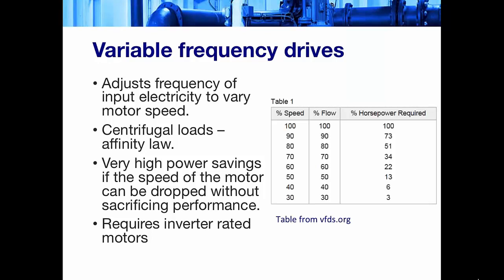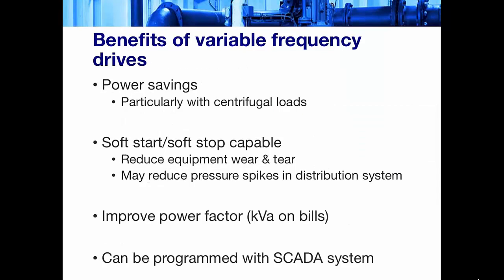It is important to note that it requires inverter rated motors in order for variable frequency drives to operate. Most newer motors are inverter rated, so there's definitely savings opportunities here. When we're looking at it, the next slide gives you some other benefits of variable frequency drives. First of all, the power savings, as shown by that chart, can be pretty strong. They also are basically soft start and soft stop capable.